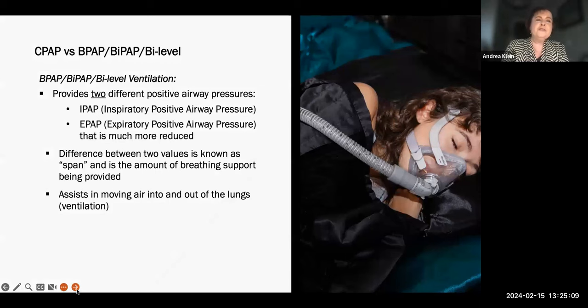So in contrast, our bilevel ventilation provides two different positive airway pressures: your IPAP, your inspiratory positive airway pressure, and then your EPAP, your expiratory positive airway pressure, which is much more reduced. The difference between those two values is referred to as span, and it's really the amount of breathing support you're being provided.